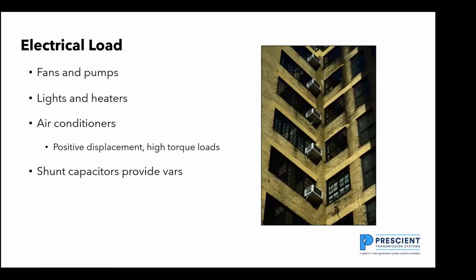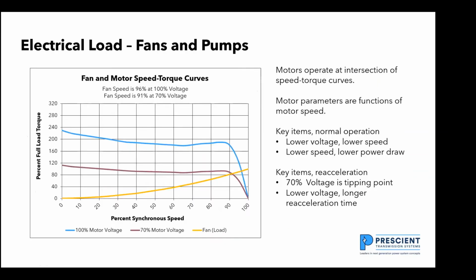So the electrical loads: I have fans and pumps, I have lights and heaters, I have air conditioners. Air conditioners are a problem because these are positive displacement pumps. They're very high torque loads, and I'm putting shunt capacitors throughout my transmission and my distribution system to provide the VARs I need. When I start looking at the loads, it's important that I look at the mechanical characteristics as well as the electrical characteristics.